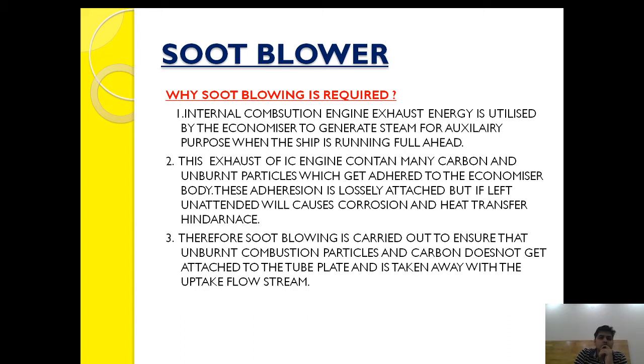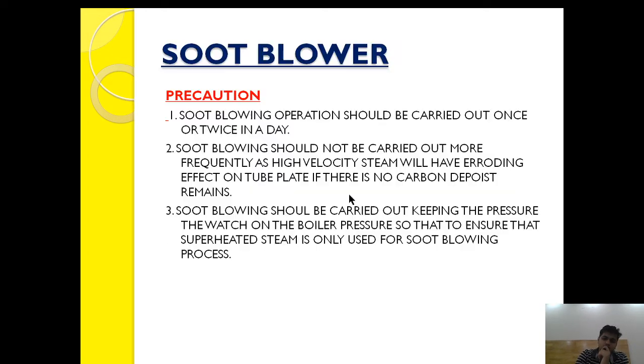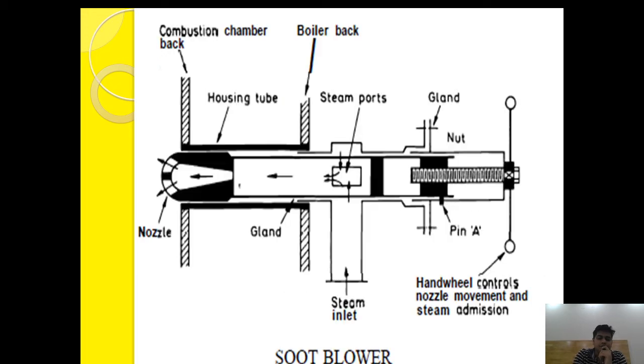The first question that comes to mind is: why is soot blowing required? The internal combustion engine exhaust is utilized by the economizer to generate steam for auxiliary purposes when the ship is running full ahead. The exhaust of the IC engine contains many carbon and unburned particles which may get adhered to the economizer body. This adhesion is loosely attached, but if left unattended, it will cause corrosion and heat transfer hindrance.